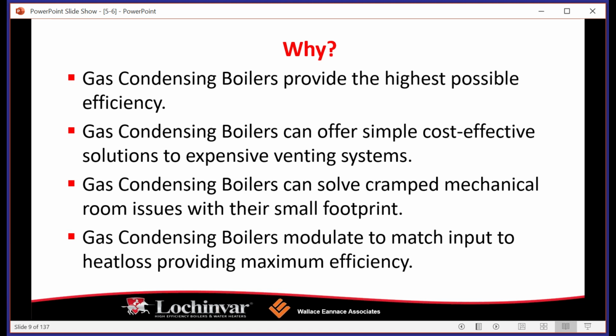We're talking about BTU inputs on our product line from 55,000 BTUs up to 6 million. And for what they are, they're very, very small. So a 6 million BTU input boiler, in past days, you would walk into a boiler plant and see it's the size of a school bus, size of a small truck. It's a very, very large piece of equipment. Nowadays, because we're able to squeak all that energy out of the heat exchangers, you don't need a giant footprint anymore. So typical boiler size, if it's not a wall hung, is a big filing cabinet at best. So again, it saves economy for your install. Your boiler plant footprint is shrinking significantly.